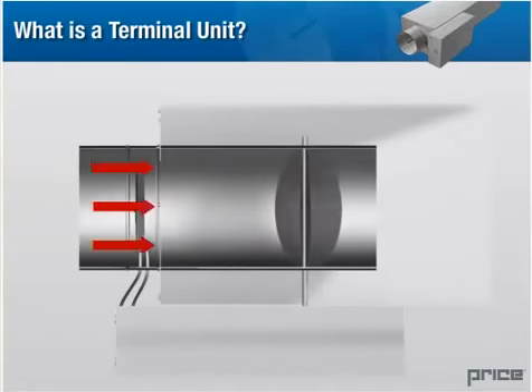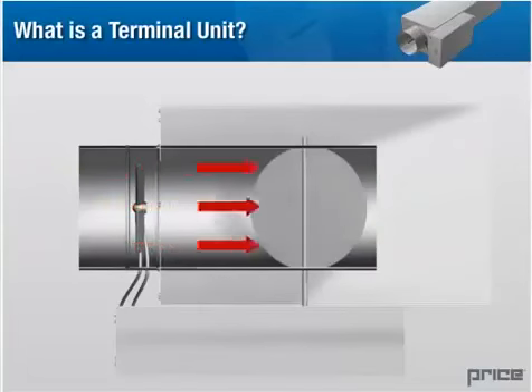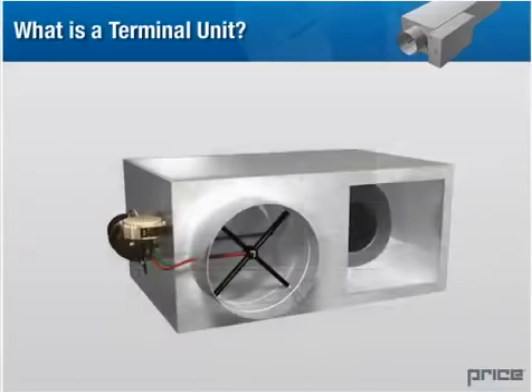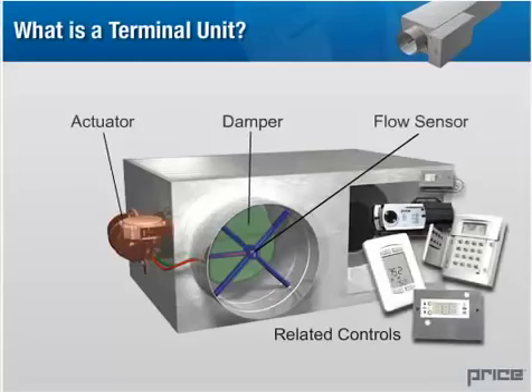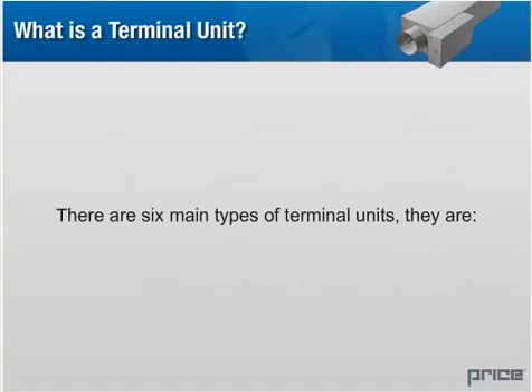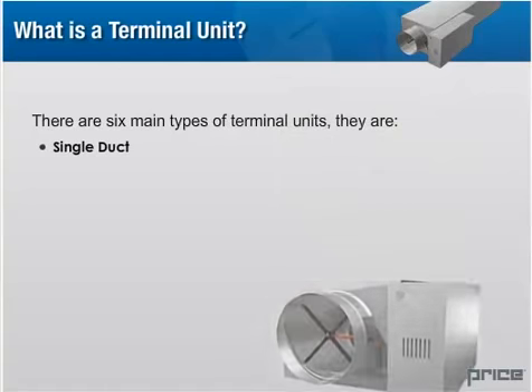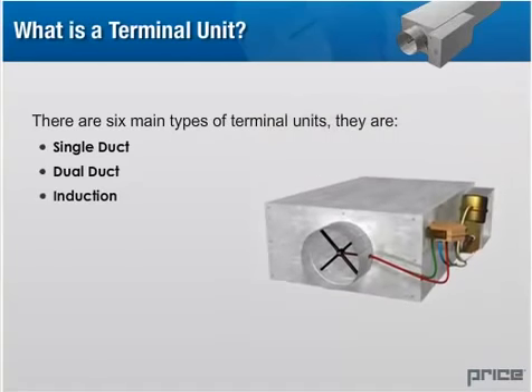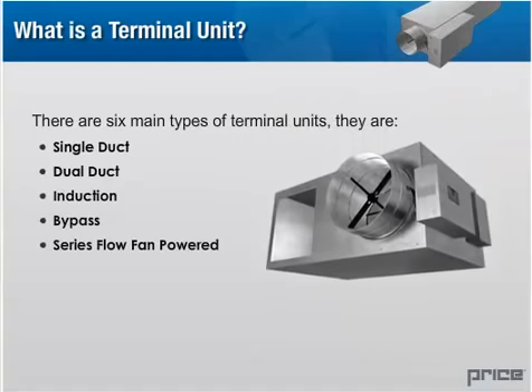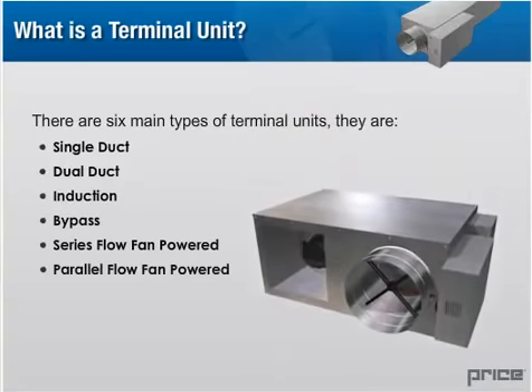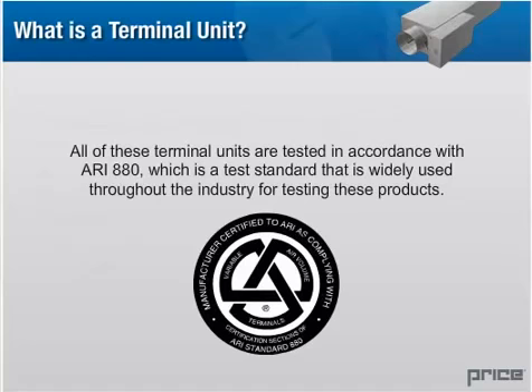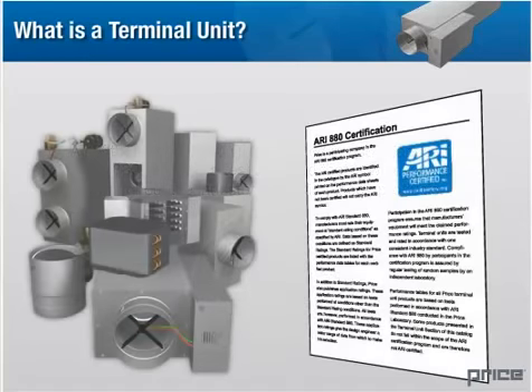What is a terminal unit? The terminal unit controls the amount of air, hot and cold, depending on the unit, that is delivered to a space in response to room temperature. The basic components are a damper, actuator, flow sensor, and related controls. These change with the type of terminal unit being used. There are 6 main types of terminal units. They are single duct, dual duct, induction, bypass, series flow fan powered, and parallel flow fan powered. All of these terminal units are tested in accordance with ARI 880, which is a test standard that is widely used throughout the industry for testing these products.